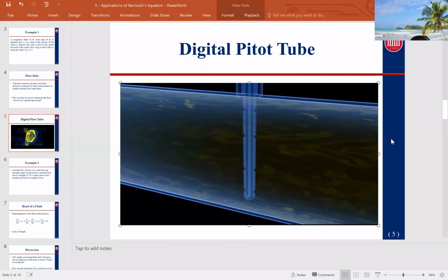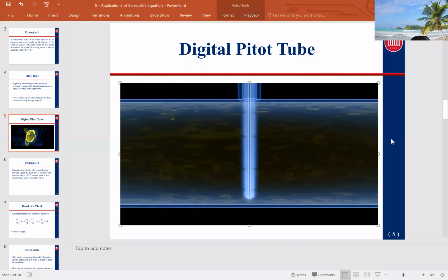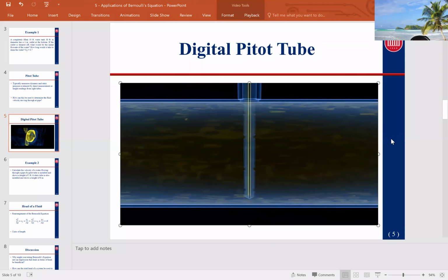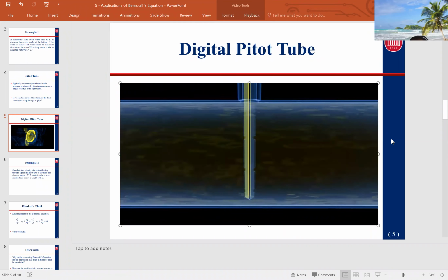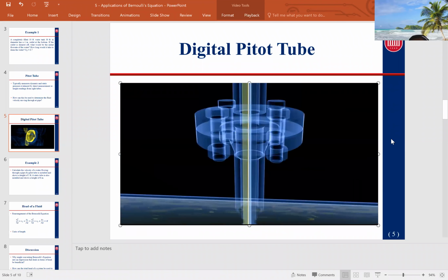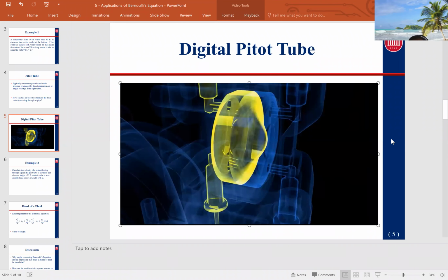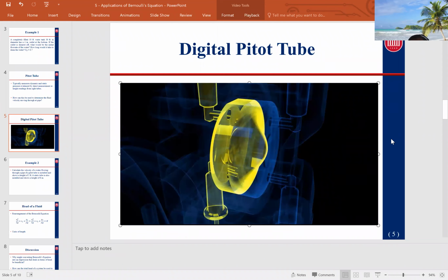If the fluid is not flowing, the pressure before and after the probe is essentially the same. As soon as the fluid starts to flow, an additional impact pressure against the front of the probe is generated, also known as the dynamic pressure. On the rear of the probe, in contrast, only the static pressure, which is not related to the flow, is still measured. As a result, different values are detected in the pressure chambers of the sensor.